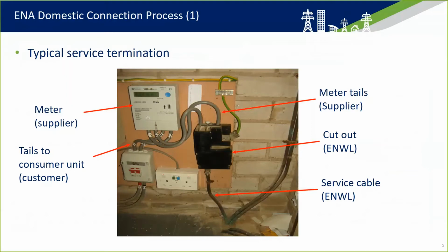Just a note on this particular one, the incoming service cable is a mineral insulated copper conductor cable, also known as pyro, which is slightly unusual. They're quite common in multi-occupancy buildings, blocks of flats and so on, but for a domestic situation, they're a little bit unusual. In this case, we would advise the installer to check with ENWL the rating of that particular cable. And you will find a wide variety of different types of cutouts, especially in older properties, anything pre-1960. Generally from 1960 onwards, it became more standard with plastic type cutouts, like the one in the photo, and more standardizing on 100 amp rating.